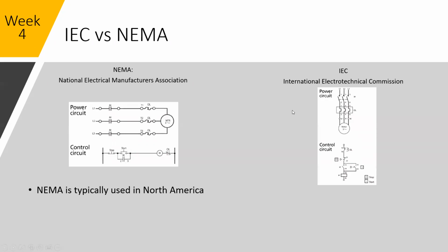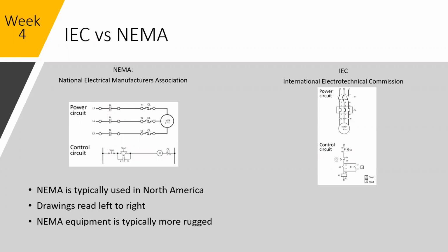So again, NEMA is typically used in North America. Drawings are read from left to right. And then NEMA equipment is typically more rugged. I say typically because it's kind of hard to judge based on the drawings. That's more of the actual physical equipment. NEMA equipment is typically larger. When it comes to electrical equipment, there's not a lot of moving parts. So when you size things up electrically, they typically have higher electrical ratings, amp ratings, different things like that.